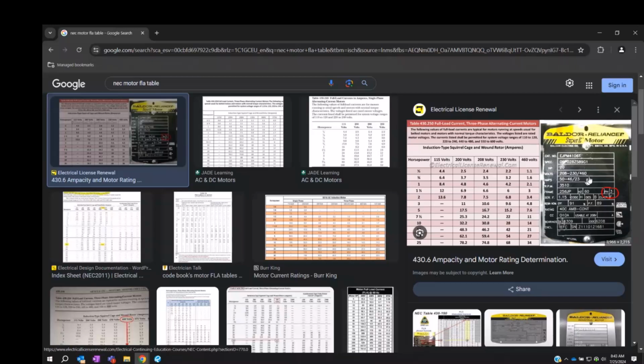Yep. And the reason we're not worried about how big of a kVA this is, is because it's actually described in horsepower. That horsepower number right there, 20 horsepower. Great. If this is a 480 volt motor, 20 horsepower, that's going to be 27 amps. So in our math, we will take 27 amps times 480 times root 3, and that'll give us kVA.